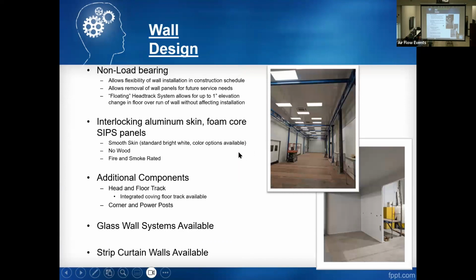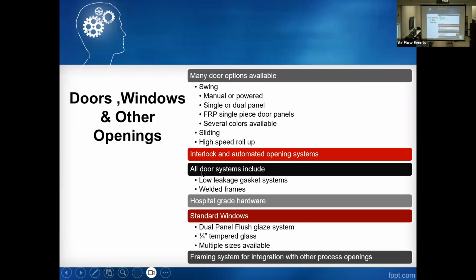Where's your return air? The return air is a low wall return air. So we actually build chases in the room, cavities with the same construction as the walls, that are the low wall returns. Again, doors, we have swing doors, double doors, sliding doors, high-speed roll-up doors.